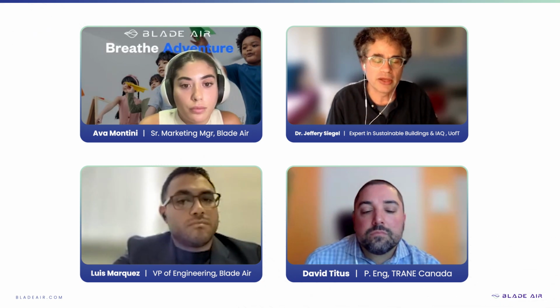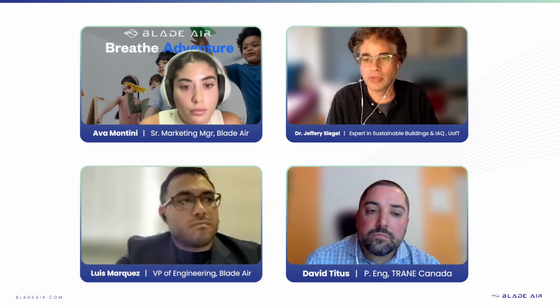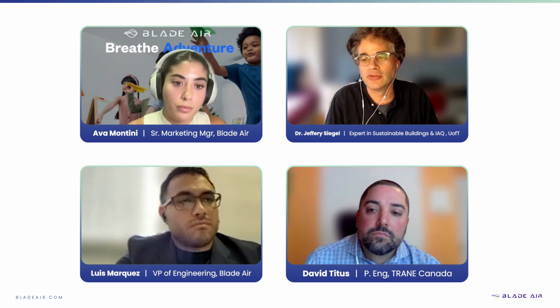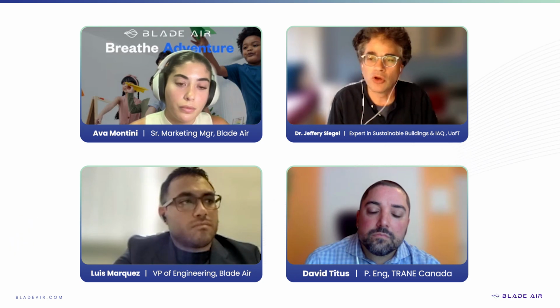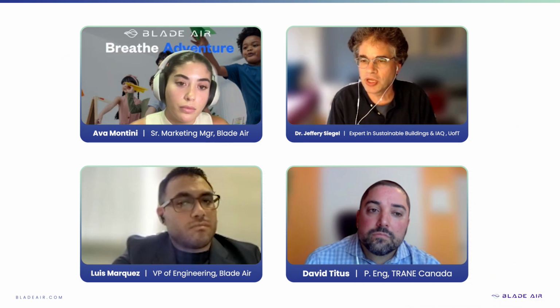The other comment is fundamentally the way a polarized air cleaner works is it produces ions. Those ions enhance removal to the filter media. And there is some evidence in the literature that ions can have some negative health consequences. Having said that, I'm not terribly concerned about polarized air cleaners because, first of all, very few ions actually escape the device. And second of all, the overall production of ions, since it's there in the air cleaner to enhance removal, is quite small. But I think that this is obviously self-interest, but I do think we need some more research, particularly on the long-term performance in actual buildings.